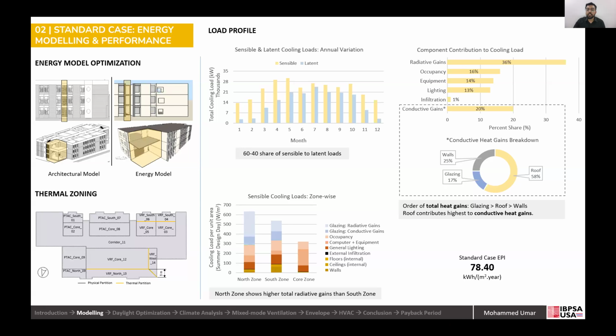But given this building was shaded extremely towards the southern side, and the north zone had a much higher sky view factor and window wall ratio than the south, the radiative gains increased much higher. Looking at the component contribution to the cooling load, radiative gains dominated by 36%, followed by conductive gains. The conductive gains, broken down at an envelope level, showed the roof element as highest, followed by the walls, followed by the glazing.